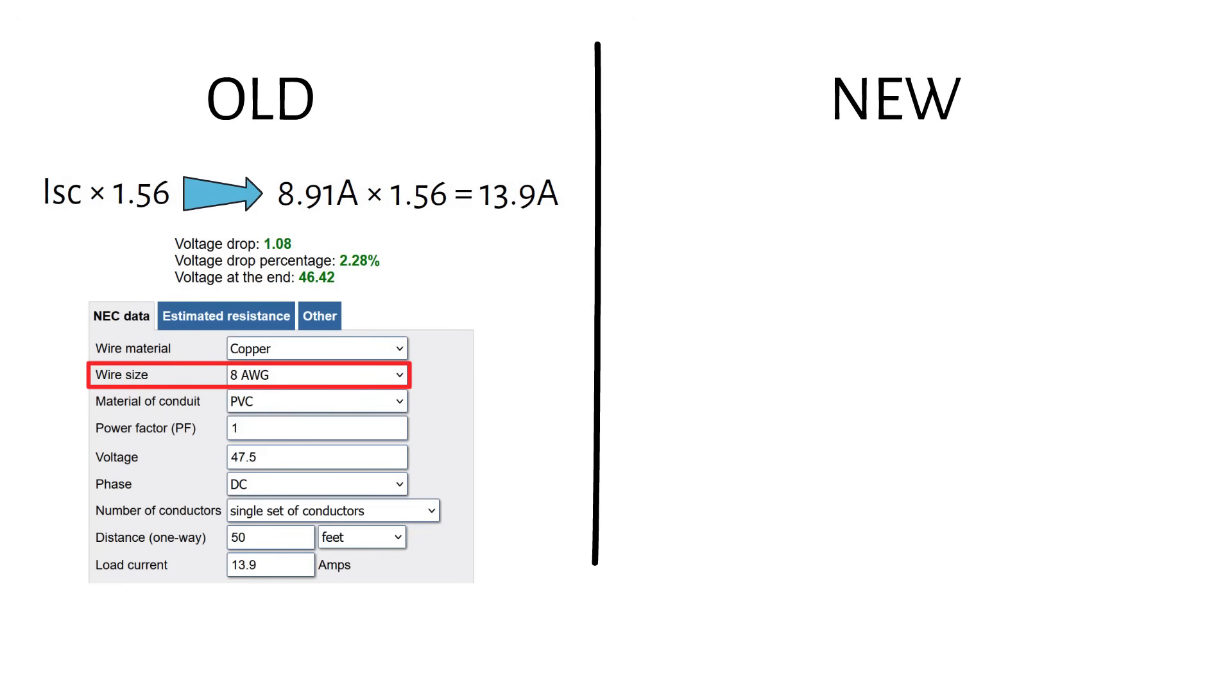And then we adjust the wire diameter to limit the voltage drop to 3%. With those numbers, the calculator tells us we need an 8 gauge or 10 mm square PV cable. And the voltage drop is 2.28%. An 8 gauge PV cable will cost you $77 for 50 feet.